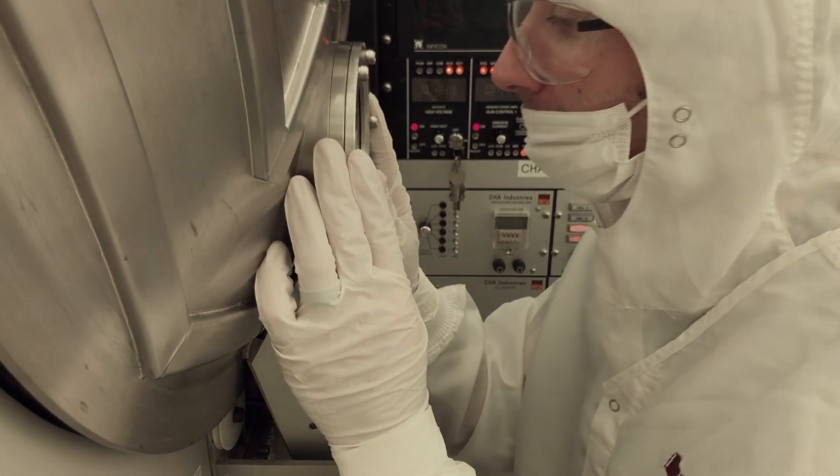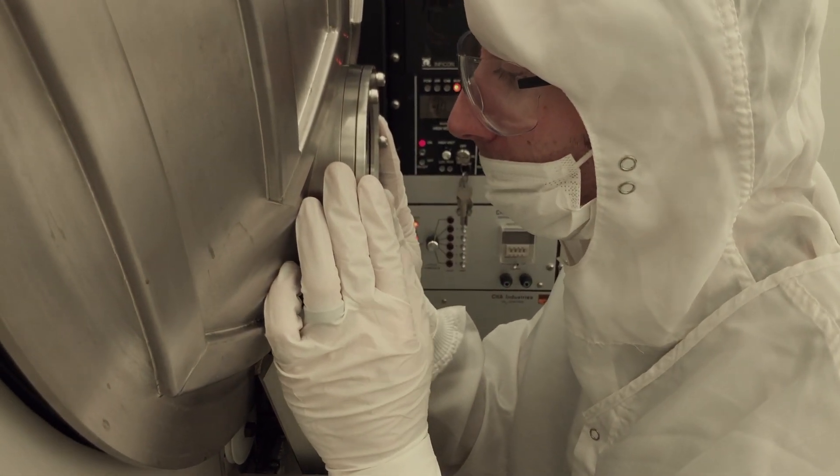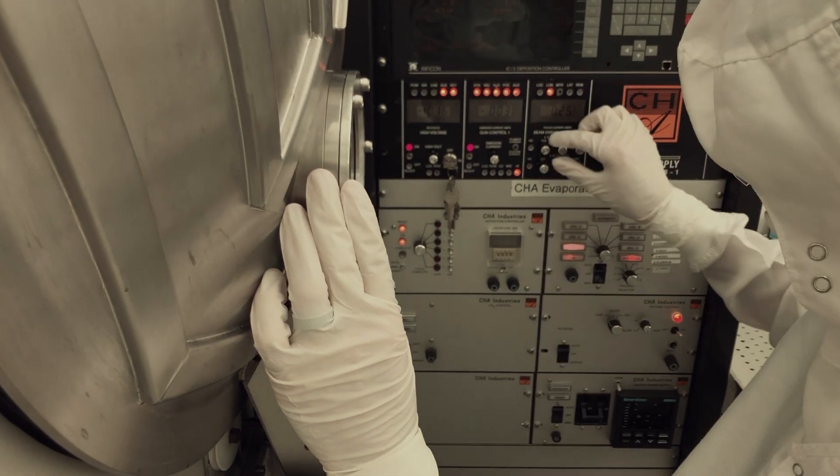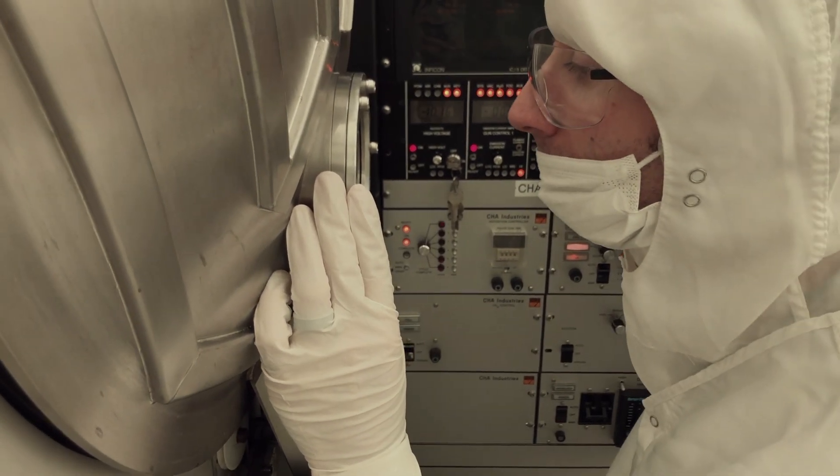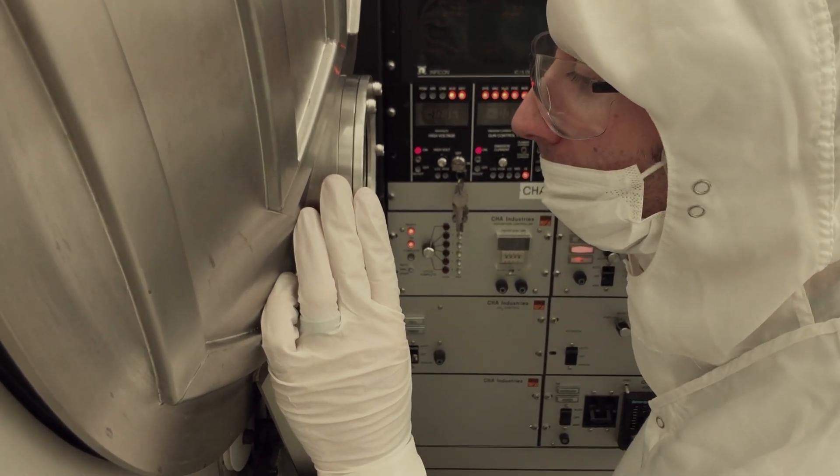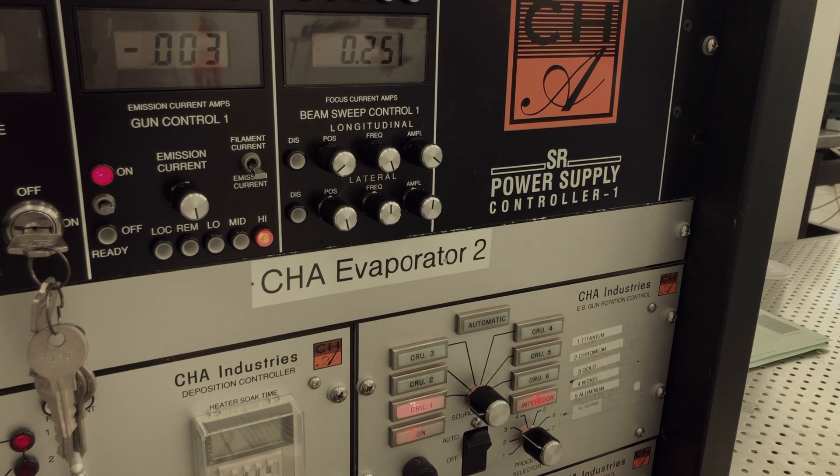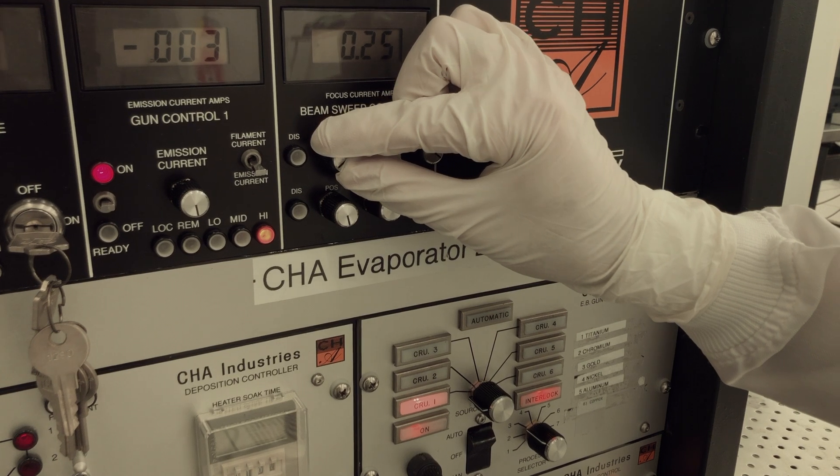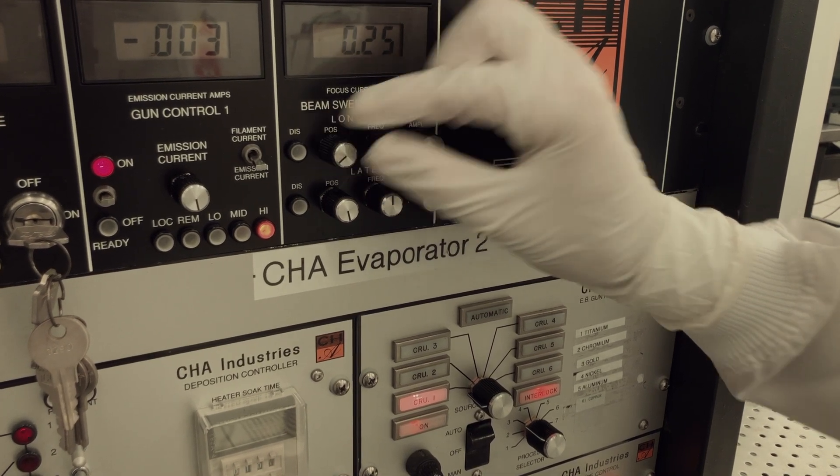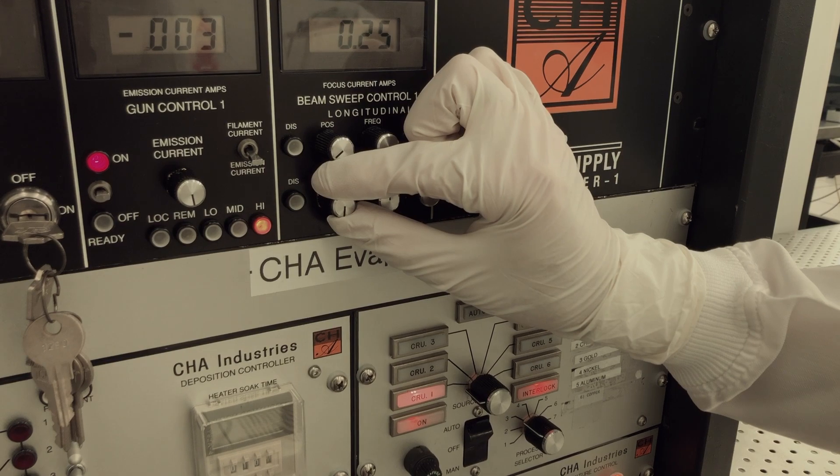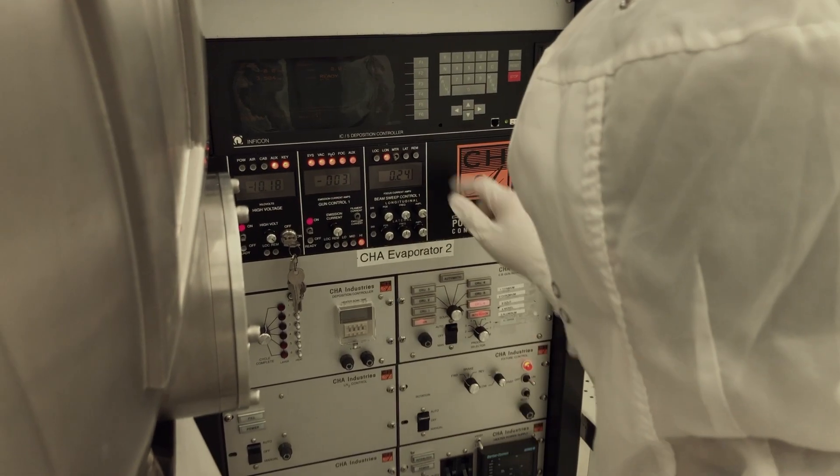Once your process has started, take a look through the viewing port on the front of the chamber. The beam pattern should be centered in the crucible. If it is not, use the position knobs on the beam sweep controller 1 to adjust the beam. The position knobs adjust the beam longitudinally and laterally. Try to position the beam before the shutter opens if you can.